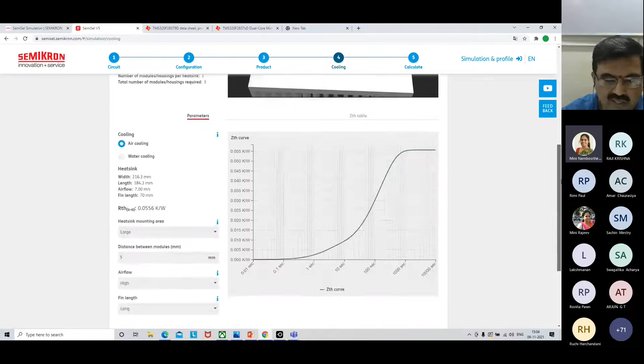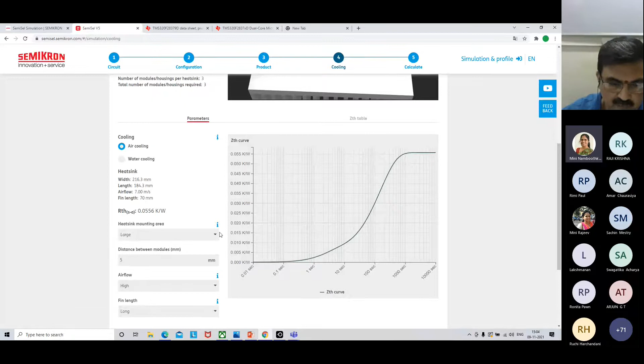So I am going for cooling, that means heatsink selection. You can see a heatsink of a particular type with 3 switches of the inverter placed out here, and ambient temperature condition - let us just take 45 degrees Celsius, because nowadays in Maharashtra also we see 42, 43, 45 degrees Celsius. I have the option to select forced air cooling or water cooling. We are going for forced air cooling. Heatsink area is large, distance between the modules is 5 mm.